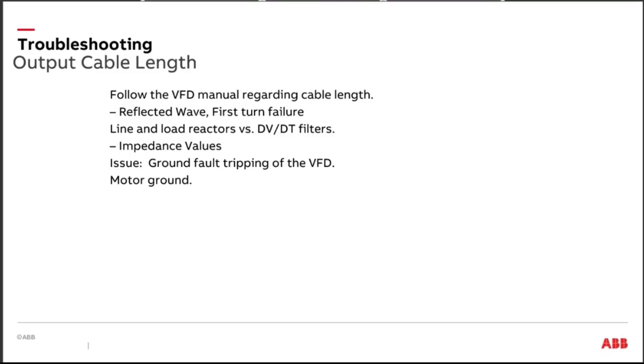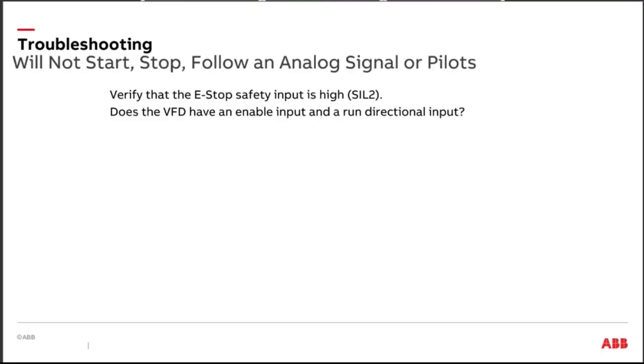If I have an old motor that's got three coats of green paint on it, and you've got to take your pocket knife and scrape the crap off the top of the nameplate, but it's still running, I'm going to use a dV/dt filter, because you don't have any idea in the world where that motor is in its lifespan, and you want to protect that motor. Okay, so those are some of the things that I think about when I start thinking about a long motor lead, and I start thinking about dV/dt filters or sine wave filters or load reactors, something along those lines. Okay, so that's where I go to there.